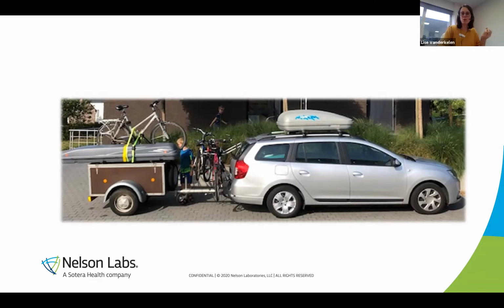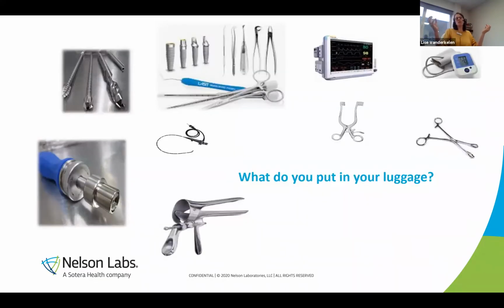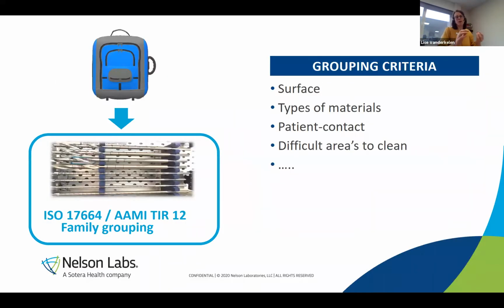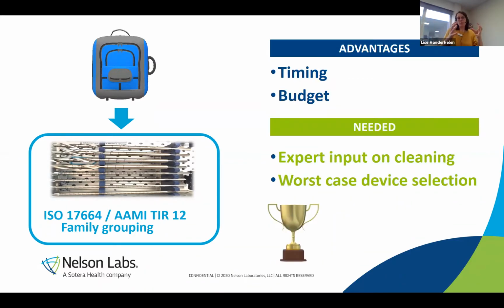Now, when you think about your reusable devices, which devices do you put in your luggage? On which devices are you going to validate your cleaning procedure? On all your devices, some of them? When you want to travel light, there is an option to group your devices into families based on the surface, the type of material, the patient-contact, and it's perfectly normal according to the ISO standards or TIR standards that you can do that. What is the advantage? You will group your devices into families and take one representative for each family on which you're going to perform your cleaning validation. The advantage is that you can reduce the timing of all your cleaning validation.